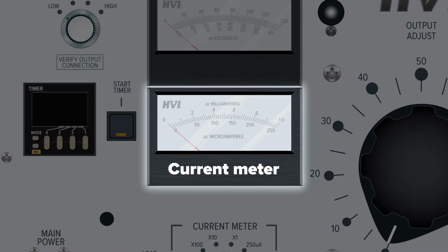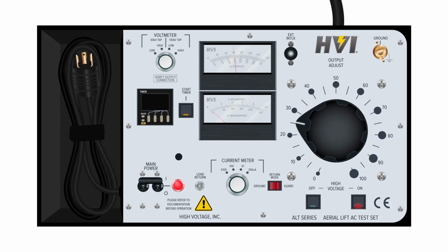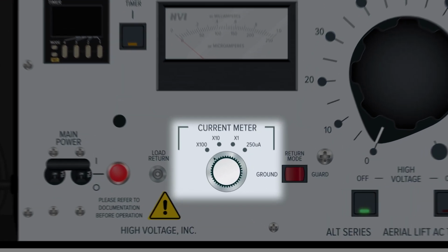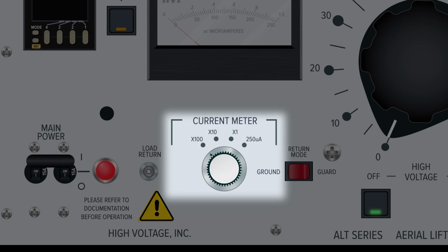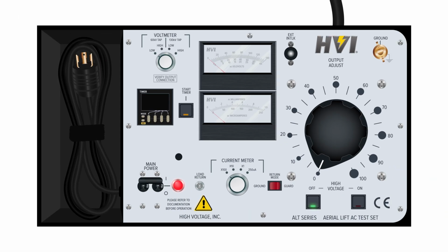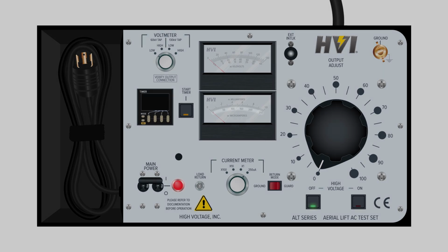When voltage is applied in a testing situation, the current meter displays the level of secondary load current being drawn by the device under test, or DUT. The current meter has four display ranges, which are controlled by the current meter range switch. When the switch is set all the way to the right, for microamperes, the meter can display currents from 0 to 250 microamperes and is read from the bottom scale.